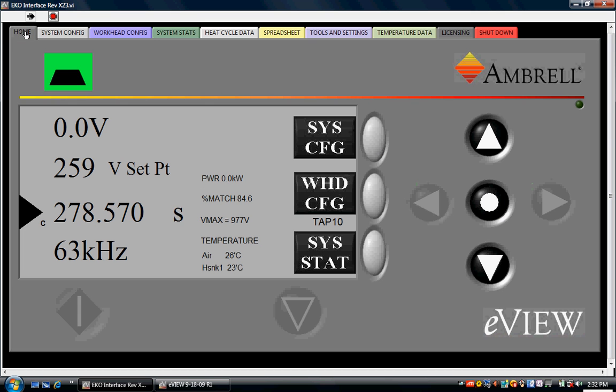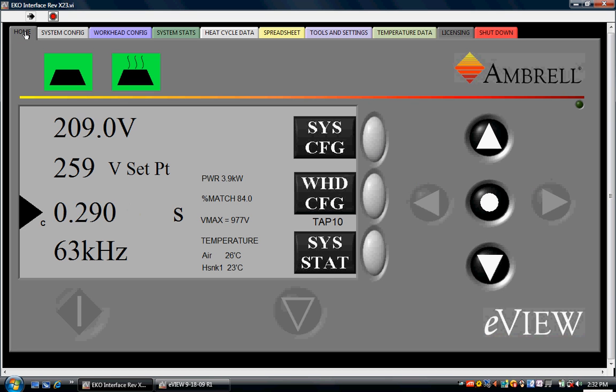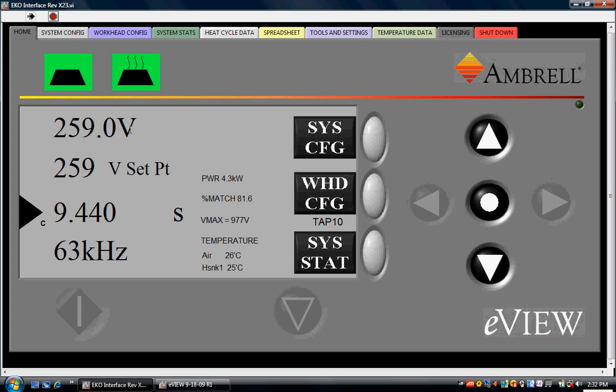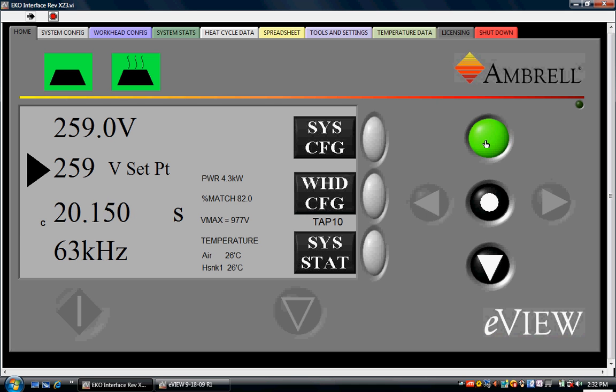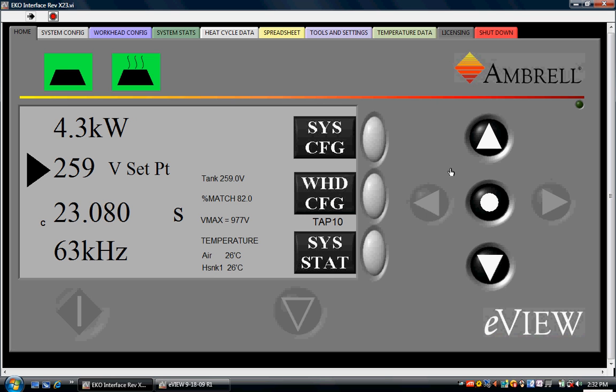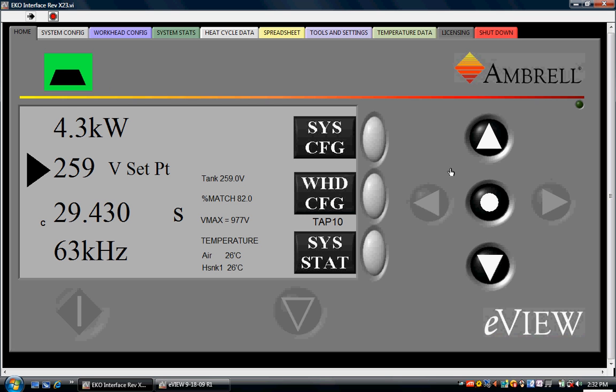We started a heat cycle from the front panel of the EKOHeat. We see that the heat on indicator illuminates and the timer counts up keeping track of how long the heat cycle is run. We are currently running with 259 volts at the coil. We can also change that to kilowatts—we've got 4.3 kilowatts at the coil. We'll go ahead and turn off the heat from the front panel. The heat on indicator goes out and our power goes to zero kilowatts.